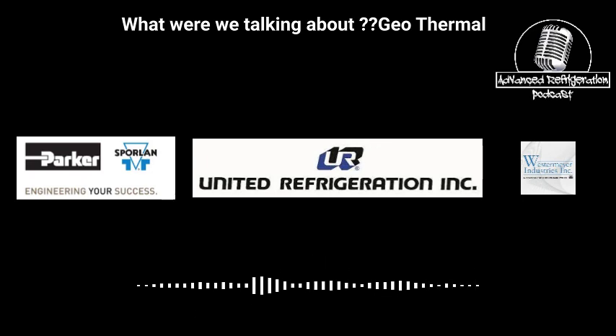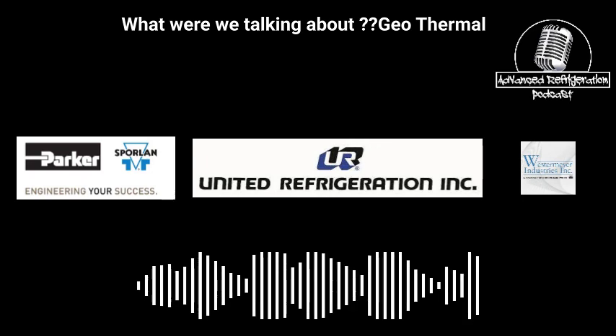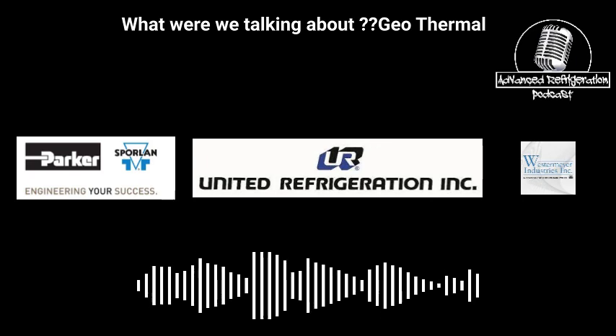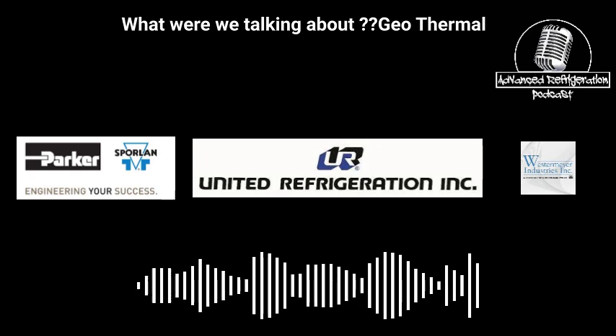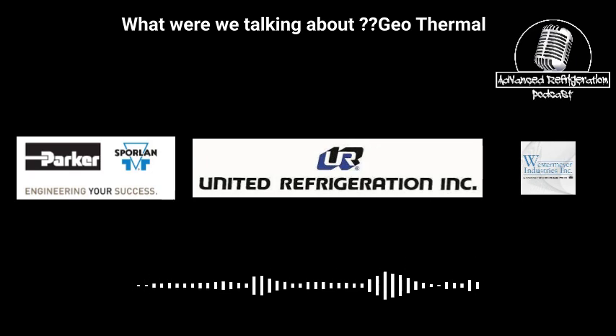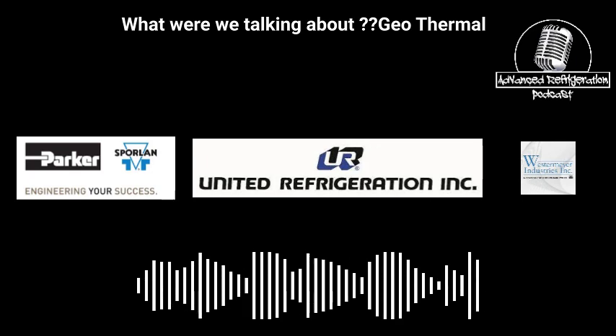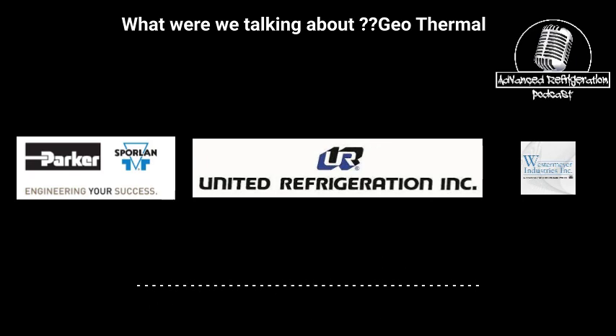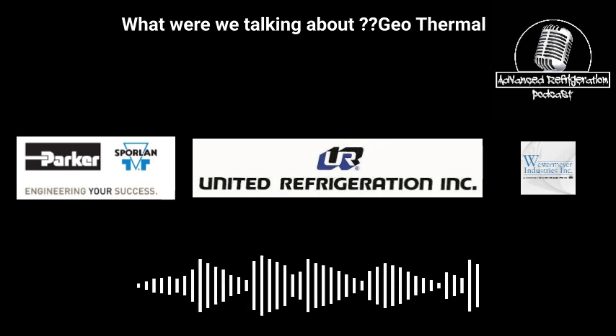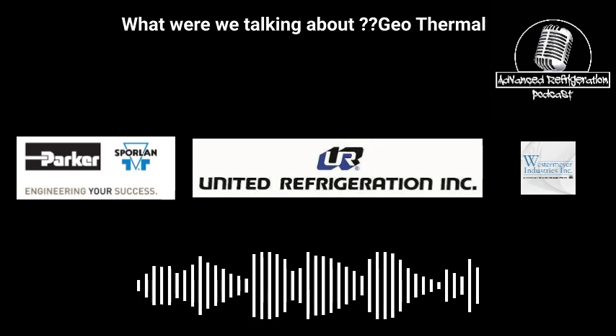Like, I mean, geothermal, if it's properly set up and the ground loops are properly sized, then it kicks ass. The issue I've seen, though, is with stores not having the ground loop sized properly, where you don't have enough water to support it, because your racks are creating heat, so you need enough water flow, which is all based on the piping and the wells, but also enough heat rejection from the wells.